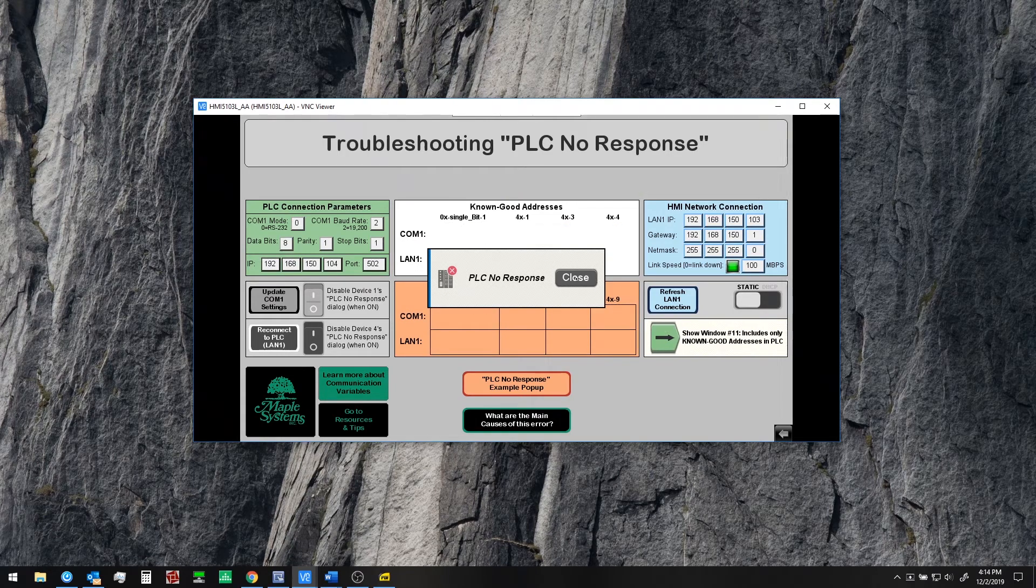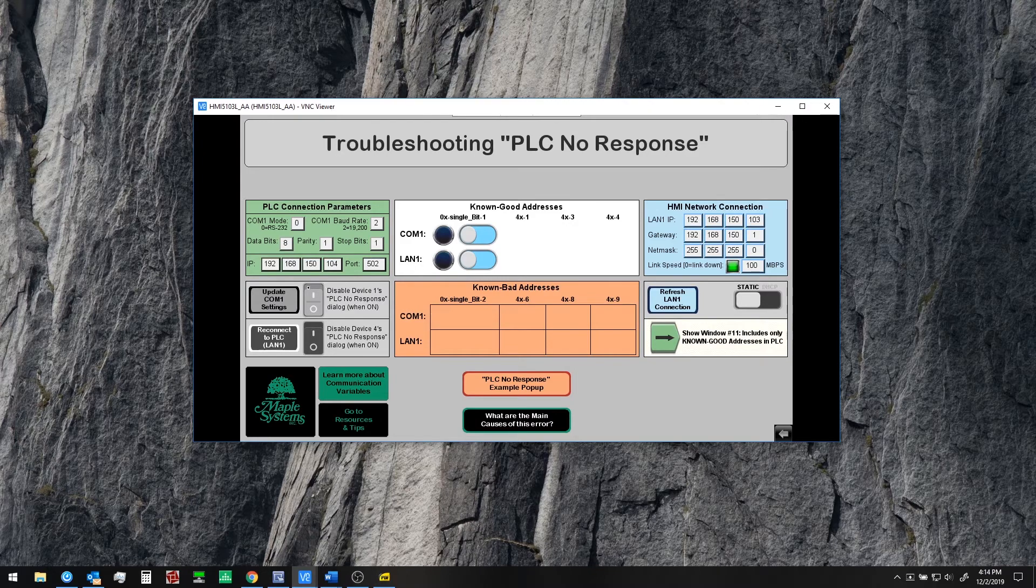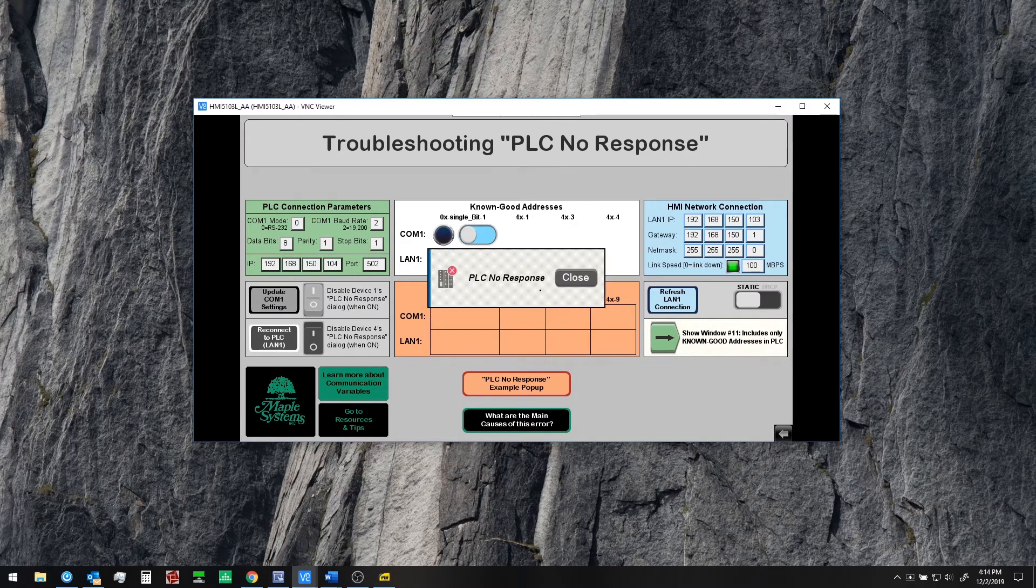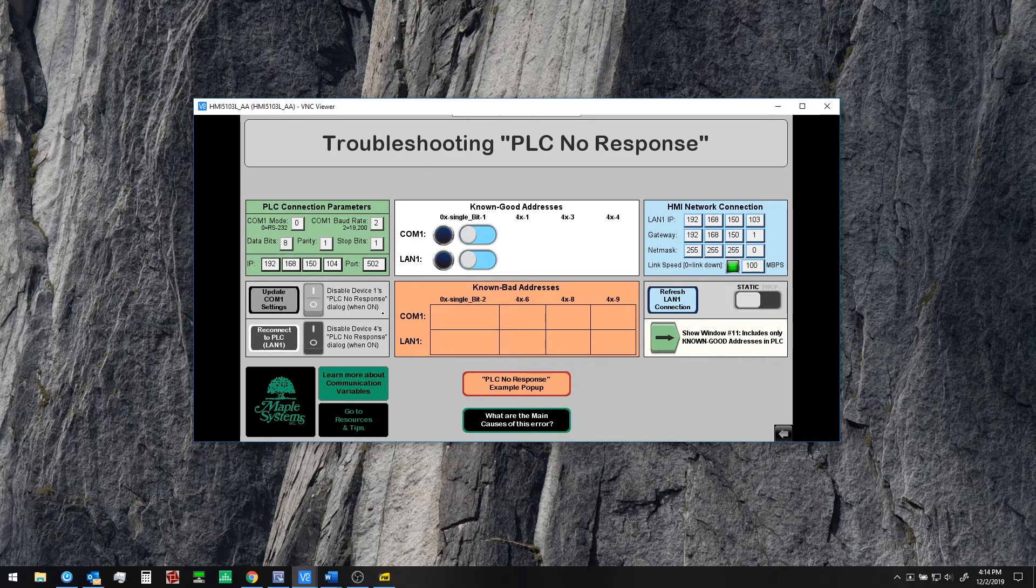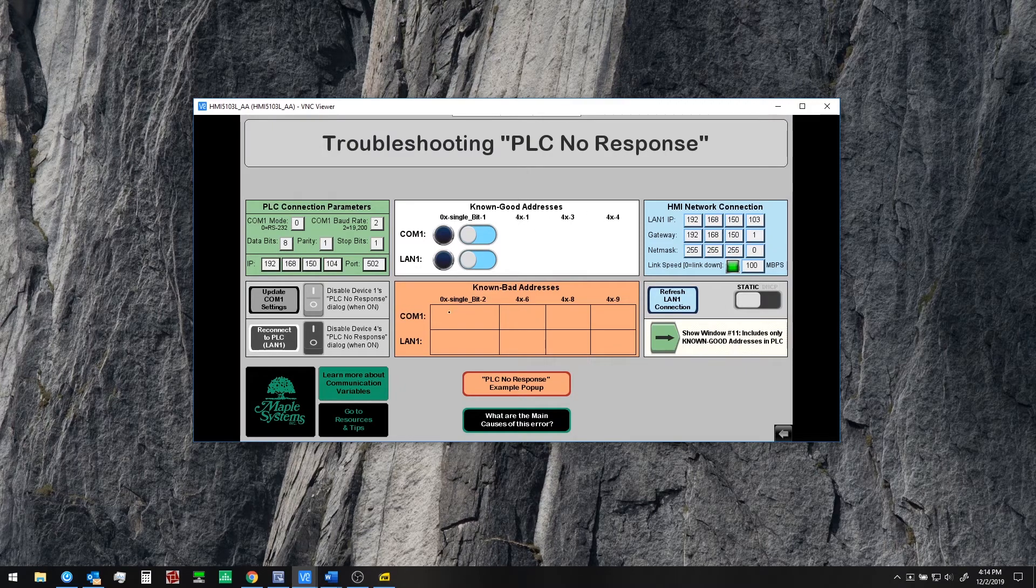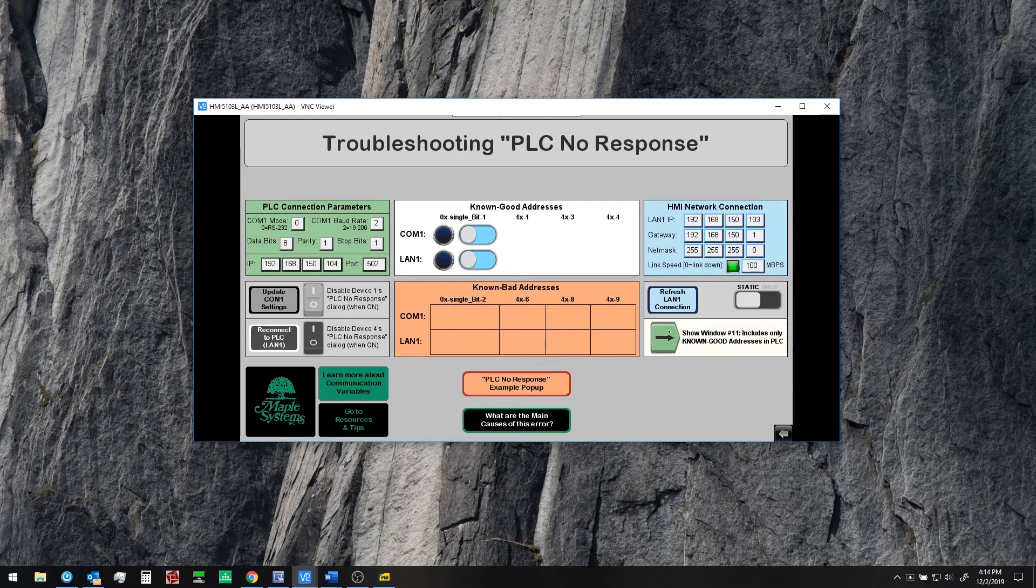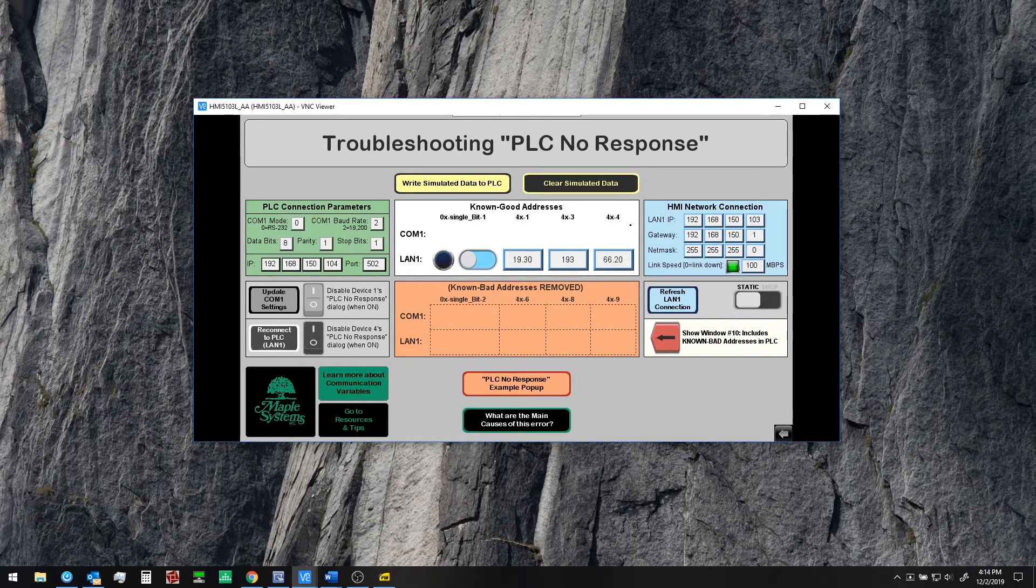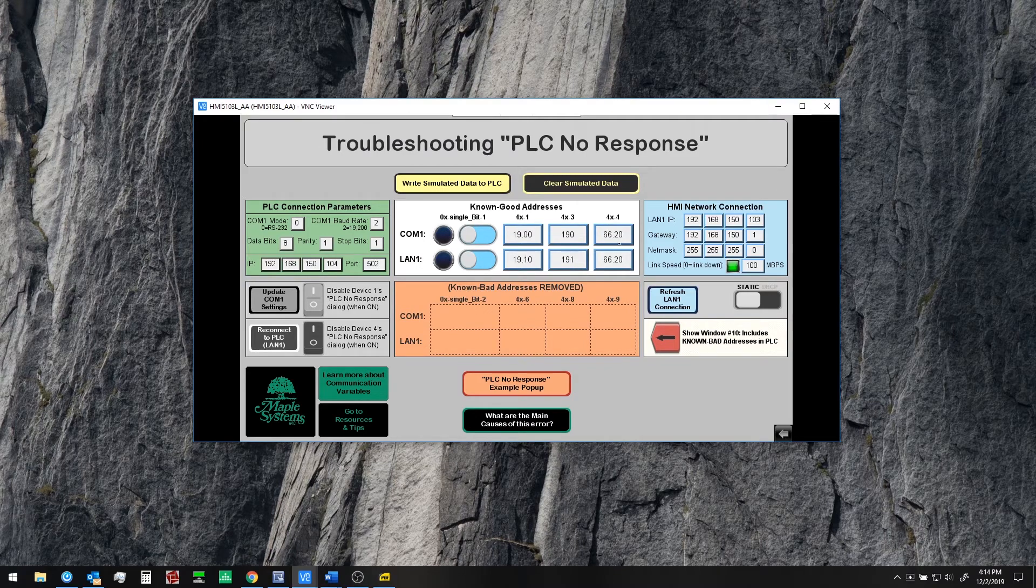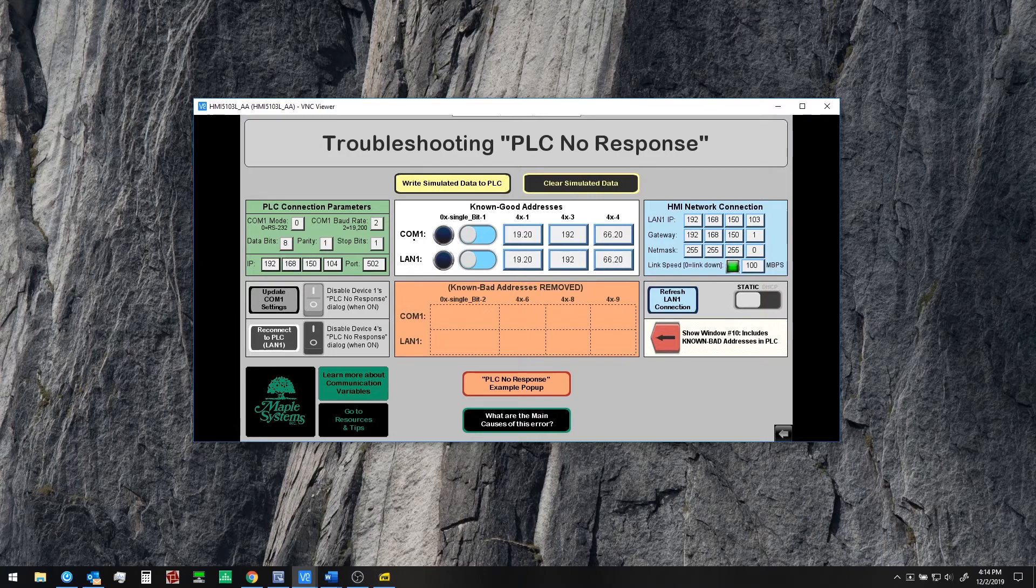Again going back to the main window we still get the PLC no response message. We can mute these notifications if we want here using these toggle switches just to keep them out of the way for a second. And again these objects are missing. Also we're missing objects here that are pointing to invalid registers. And again when we go back to our window 11 the data is appearing here and then after a moment it starts to appear here too on the other interface.